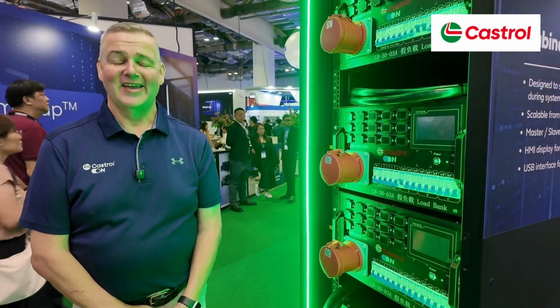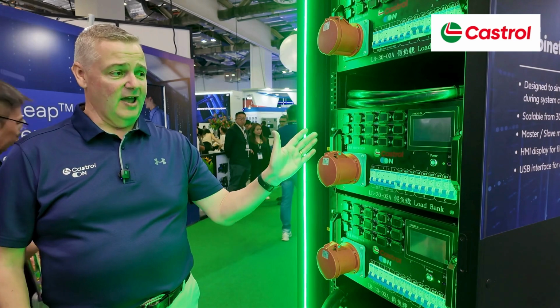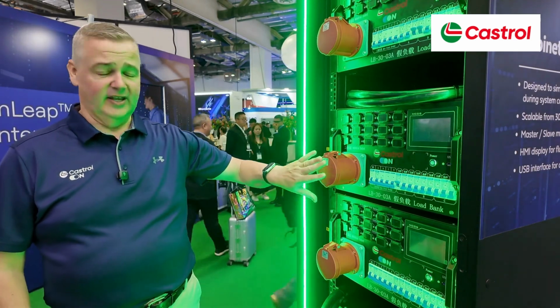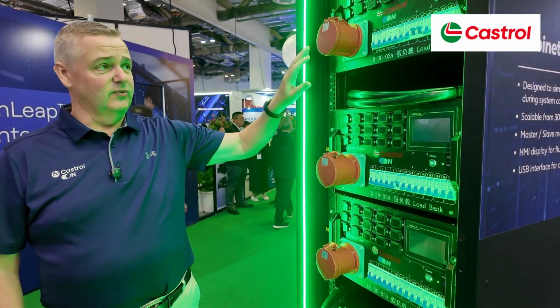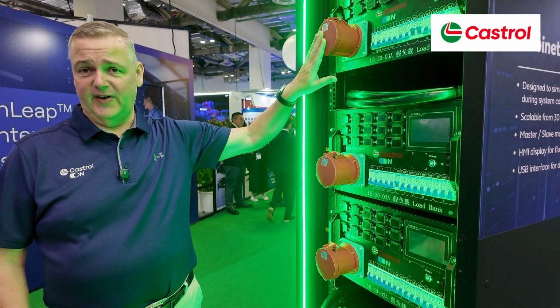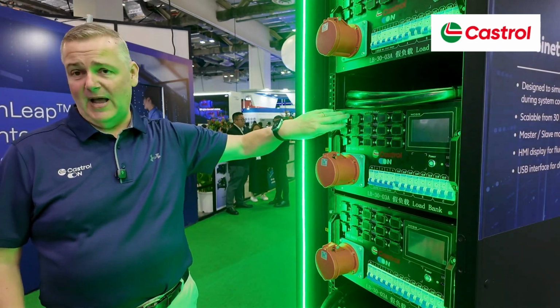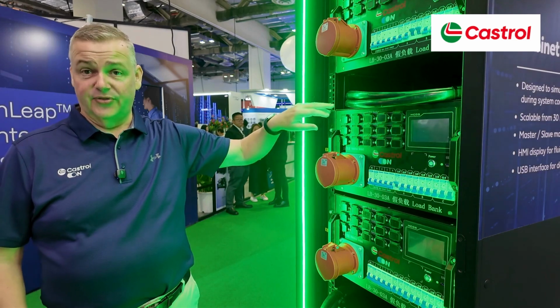Right, Mark, you brought me round to the front of what looks like a substantial bit of kit. Can you talk me through it? Yeah, absolutely. The unit you're looking at is a liquid load bank, and this fits into the commissioning phase of the end-to-end services. The front of the rack is where we bring in the power, and it can either be a 63 amp three-phase connection, or we power these individual sockets through a three-phase PDU.